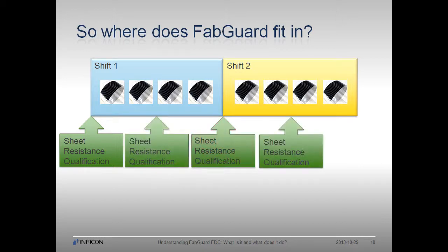We can mitigate this risk by increasing the frequency of qualification — for example, performing it every 6 hours instead of 12 — but this is expensive in time and money, not to mention the loss of productivity. Practically speaking, we need to augment qualification data with information available on a lot-to-lot, wafer-to-wafer, or real-time basis to actively lower our risk of scrap. This includes data collected from the tool as well as any advanced sensors attached to that tool, and that's where FabGuard comes in.